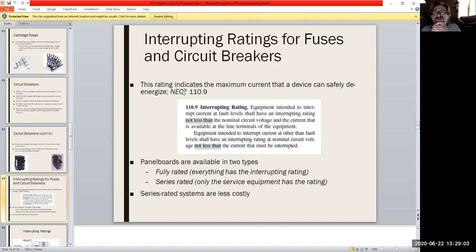So if we look at Article 110, Section 9, equipment intended to interrupt current at fault level shall have an interrupt rating not less than the nominal circuit voltage and the current that's available at the line terminals of the equipment. And it says here, equipment intended to interrupt current at other than fault level shall have an interrupt rating at nominal circuit voltage not less than the current that must be interrupted. So basically you can't put something on this line that's going to exceed this rating. Otherwise your device is going to constantly de-energize. So your line has to be designed in a certain way, and the devices that go on that line have to comply with those rules.